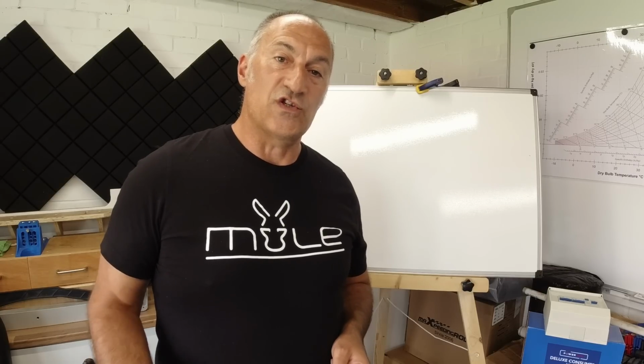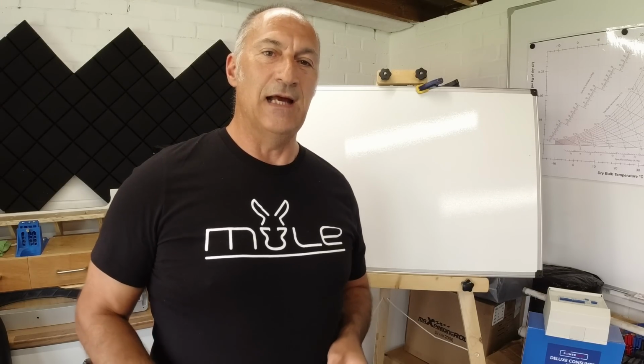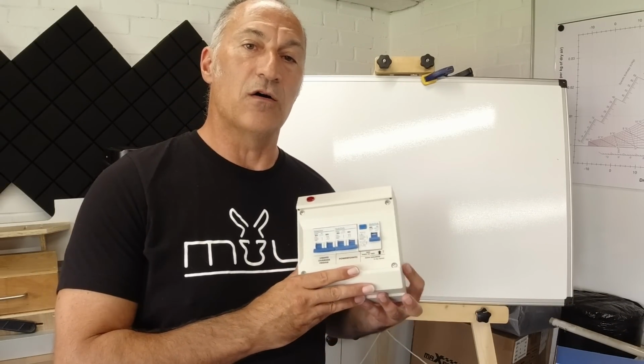If it's a short circuit and a lot of current flows, obviously that's going to heat up really quickly, and that little solenoid in there is going to trip the MCB almost instantaneously, or literally within a fraction of a second. Now there's one other point that has been discussed widely on various forums, and that's the need for the consumer unit to be housed in a metal box.